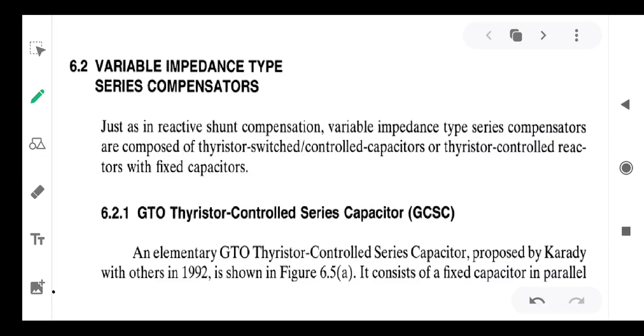The function of the TCR is to control the current injected by the device into the system. By continuous control of the conduction angle, the turn-on angle or turn-on time, we can control the current through the TCR, which is non-sinusoidal, and it injects current harmonics into the system. All of you are aware of that. Whereas here, the voltage waveform of the capacitor voltage can be controlled with the turn-off time of the GTO. The voltage waveform is now similar to that of the TCR current waveform. Now GCSC will inject voltage harmonics into the system, like TCR is injecting current harmonics into the system.